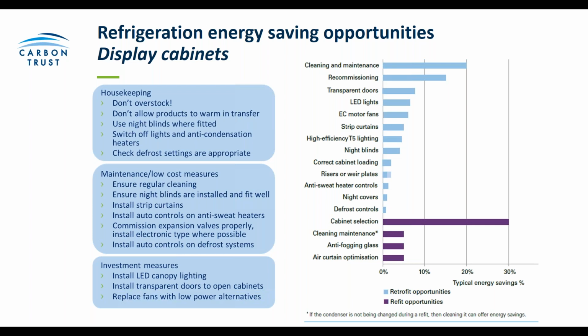It's important to make sure that night blinds are well fitted and covers on all cabinets are available to reduce the load during non-trading hours. Think about fitting anti-mist film or spray and switching off the heaters permanently at times when it's not needed. Ensure all the expansion valves where you've got them are properly commissioned, and if possible use the electronic type. So these will be the most efficient type that you can use.